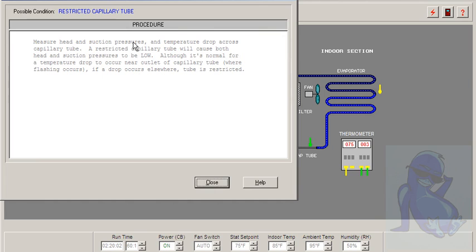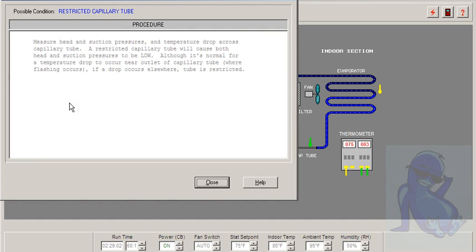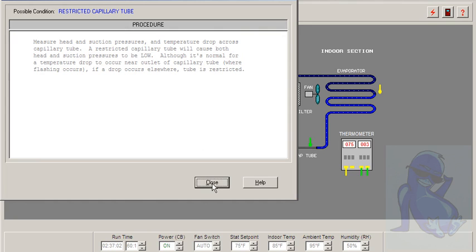Measure the head and suction pressures. The temperature drop across the cap tube. Restricted cap tube will cause both head and suction pressure to be low. Although it's normal for a temperature drop to occur near the outlet of the cap tube where flashing occurs, if a drop occurs elsewhere, the tube is restricted.